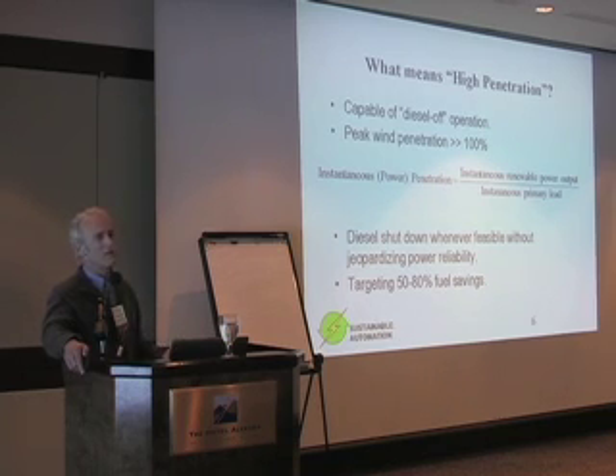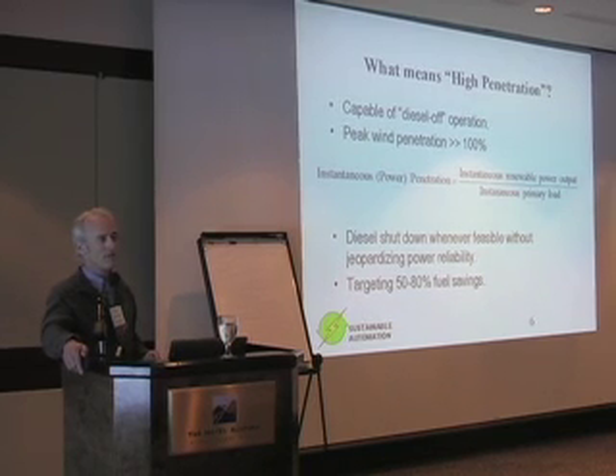You'll hear a lot about low load diesel operation this week. One issue around that is, yes, it's feasible, but much of the operating cost of a diesel, or certainly much of the maintenance cost, is a function of run hours, not load levels. So if that machine is online accumulating hours, you still have to do the oil changes. You still have to do the major overhauls at a certain set number of hours. So we like to keep them shut down.